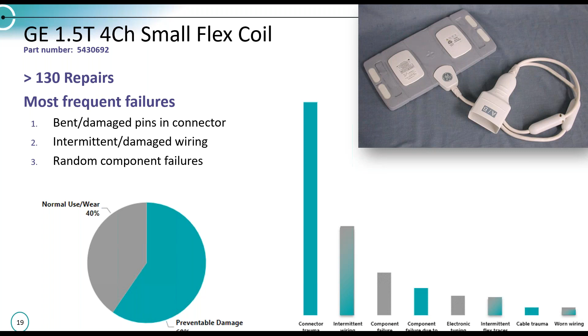And then a lot of the next type of damage is just related to wiring. So it could just be continued flexing, sort of that gray area that occurs, the intermittent wiring. It just could become overly flexed cables, or in combination with a pull or a crush, something like that. And then thirdly, we do have some random component failures. But by far, connector damage far outweighs any type of random component failures or even tuning events that occur from the components inside this coil.